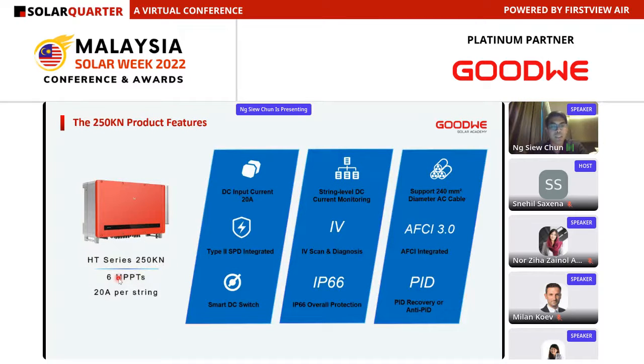And moving forward is our inverters, the 250 kilowatts, like I mentioned. We actually have two series, the 250K HT or 250K NHT. The 250K NHT is the latest product that comes with 6 MPPT, and with each MPPT we have 3 strings. So each string will support up to 20 amps of current. So why would we need the 20 amps? As everyone knows, the current 210 mm high performance modules have current mainly in the 18 or 19 amp region, especially from Trina Solar or Risen Solar and so on.